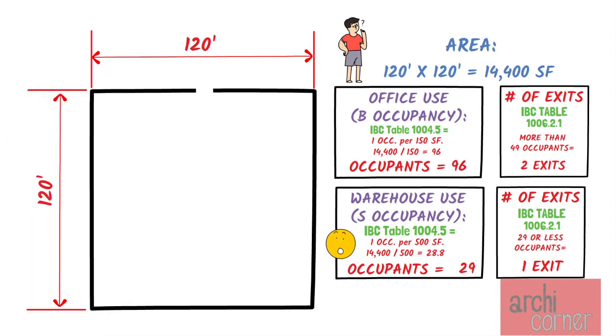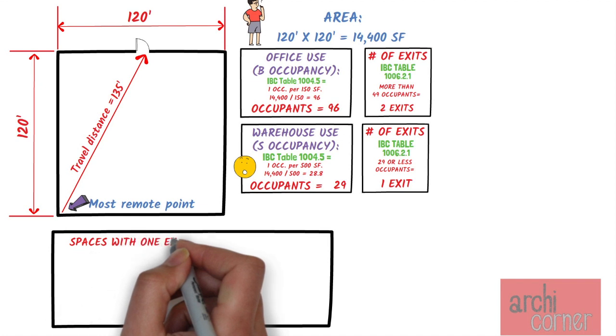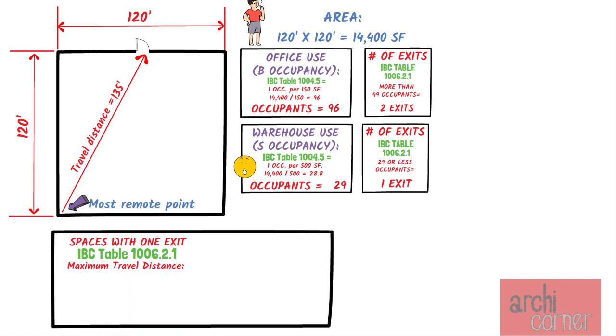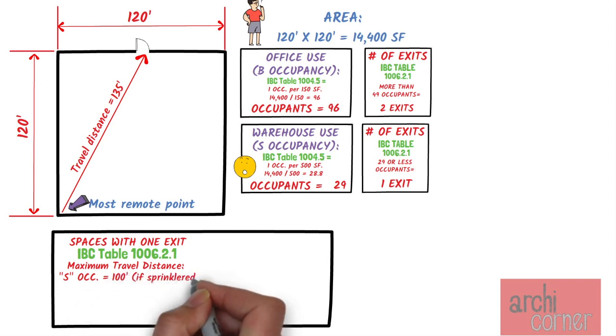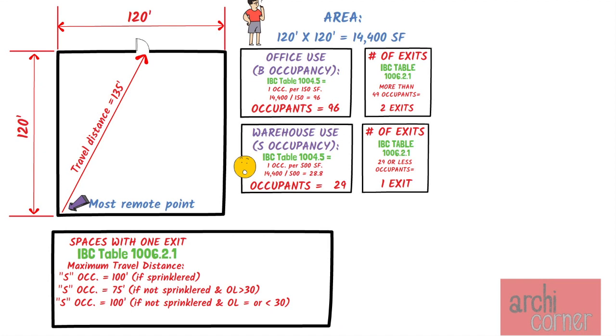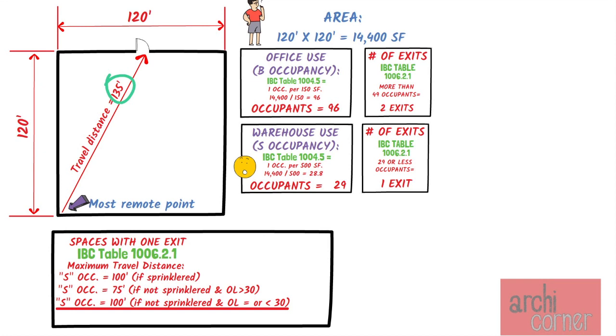Assuming this space is used for warehouse, we place only one exit. Now let's determine the travel distance. Starting from the most remote point of the space, even if there are no obstructions and a person can access the door in a straight line, the travel distance would still be 135 feet. Looking at IBC Table 1006.2.1, the maximum travel distance for warehouse — normally classified as an S occupancy — is limited to 100 feet if the building is sprinklered, 75 feet if not sprinklered with an occupant load greater than 30, or 100 feet if not sprinklered with an occupant load of 30 or less. Since we are limited to 100 feet, we are not in compliance with the building code.